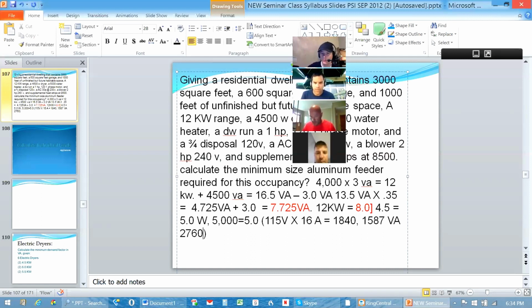So I'm going to go back here and adjust this one by 125%. 3450, and that's what I'm going to use in lieu of this 2760. So this is a connected load. This is a demand load, and it just so happens that our demand factor is more than 100%. So it can do that. It can go up or down depending on your factors. So this will actually be the value that we're using for that one. And to pick those other ones up, we had, let's see, this 1840 at 100% and the 1587 were the other 2 we're going to pick up there. We also had the 5000 for the water heater at 100%, and we had the dryer at 5,000 watts as well. All right, that is everything except the air conditioning and heating.